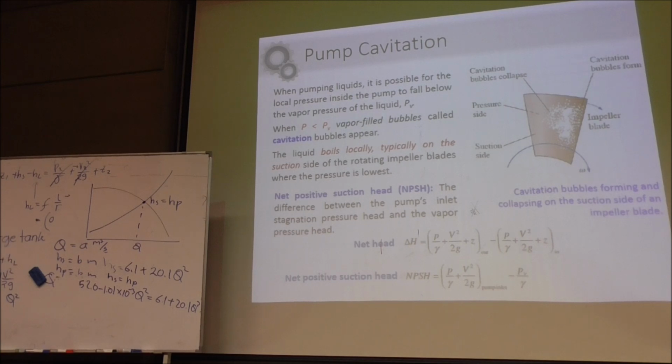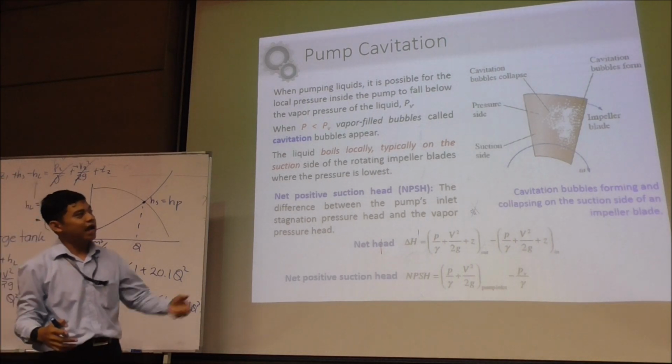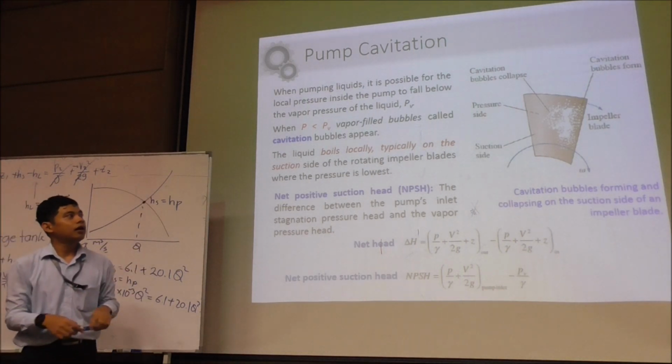Now you can imagine when a cavitation bubble forms in the center of the pump and moves to the trailing edge, the pressure is getting higher, right? So what will happen? It will collapse. It will pop, break, burst, whatsoever you call it, right? It seems harmless if it is only one or two. But if you have a million of them and it happens all the time, you get those so-called...